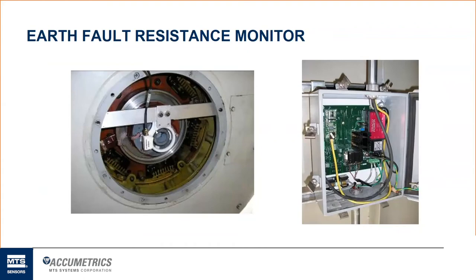So there are turns of wire on the ID of this white pickup antenna, and on the OD of this gray transmitter snout. That is what makes that connection to form the rotary transformer between the rotating world and the stationary world. We transmit that across approximately a 3/8 to 1/2 inch air gap, and then we're bringing power back the other way to power all of our electronics out on the rotor. So you don't need any battery or power source out on the rotor itself. Everything comes from the stationary side, and that digital data comes back and runs off to our receiver.